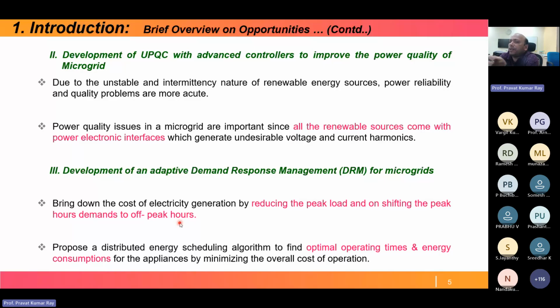So when power quality deteriorates, our aim and objective is to improve the power quality. If we are more concerned about current quality improvement, we have to go for an active power filter, a shunt active power filter. If we are more concerned only about voltage quality, we have to go for a series active power filter. But if we require both voltage and current quality to be good, or want improvement in both cases, we have to go for UPQC, where both series and shunt active filters are present.